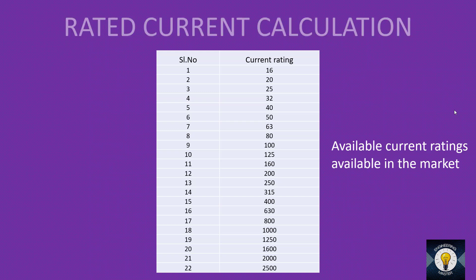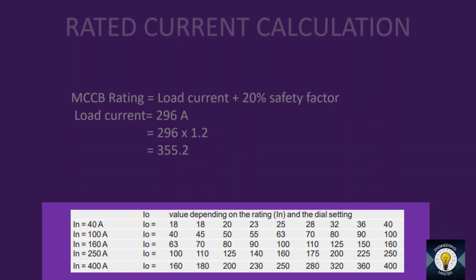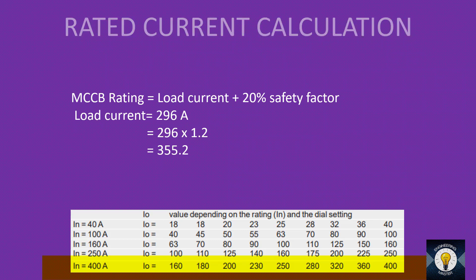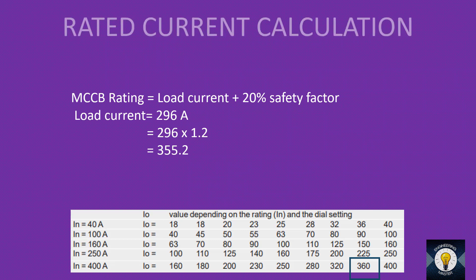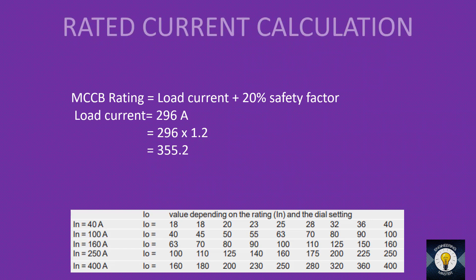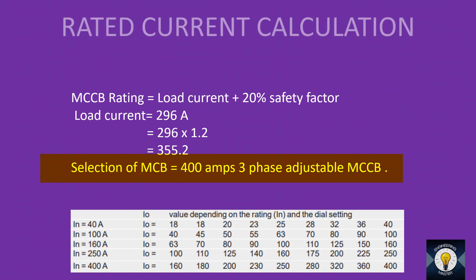Looking at the catalog, the 400 A breaker is available with adjustable current settings — nine settings from 160 A to 400 A (160, 180, 200, etc.). Inspecting the table, we can see 360 A is available. Our required rating is 355.2 A, which is very close to 360 A. So we select a 400 A three-phase adjustable MCCB and adjust its setting to 360 A.